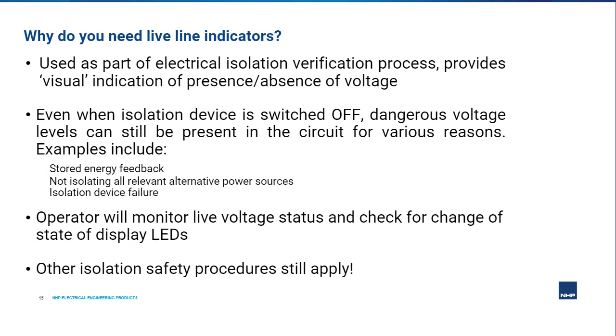Now, this is where the REMLIVE unit can help assist the service technician. Say the REMLIVE unit is installed, wired, and available on the panel, and the service technician switches off a load or loads using the isolating switches or circuit breakers. If there is still dangerous voltage levels present in the circuit, due to the reasons mentioned before, then the REMLIVE unit will indicate this to the user as the LEDs on the unit will turn on. The expectation then will be that the service technician takes further measures to identify reasons for why correct isolation has not occurred and address these issues. By acting upon this correctly, the user can expect the REMLIVE status LEDs to change state from on to off.